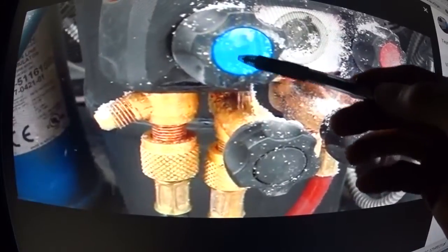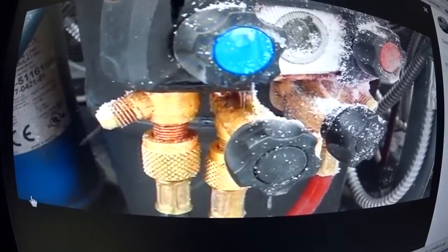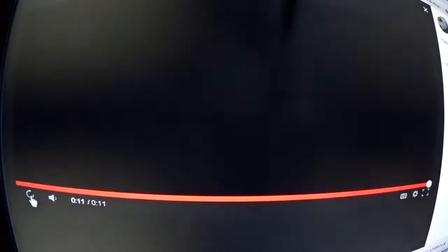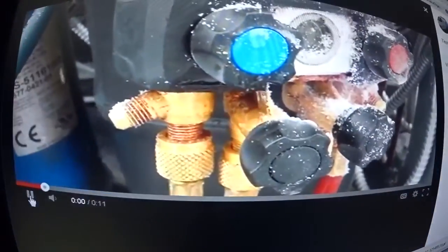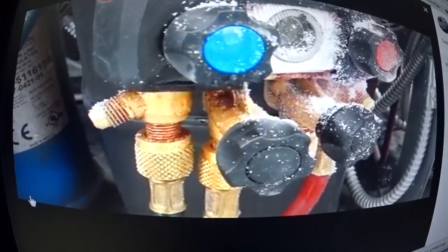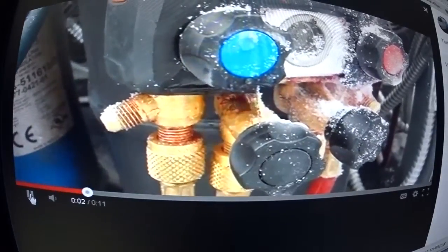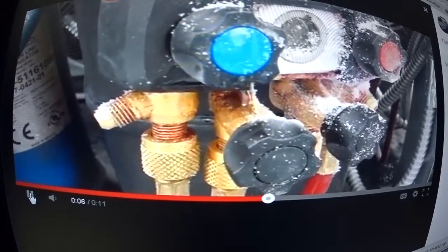You can see here the gauges are leaking liquid — there's liquid coming out of the high side post over here. The o-rings on the post are leaking, and I'm losing as much gas as I'm putting into the system. I could have gone to the truck and gotten a heater to warm the tank up and get the pressure up, but I was too lazy and too cold at that point, so I just forged through it to get done.